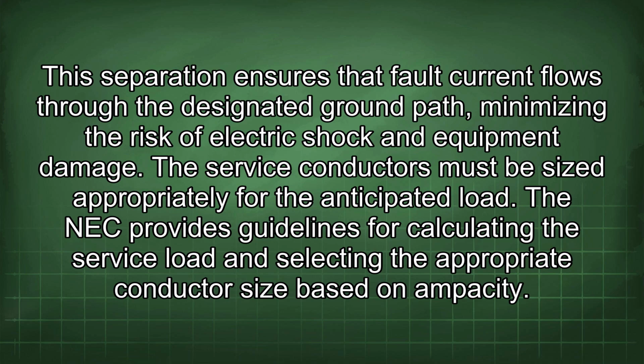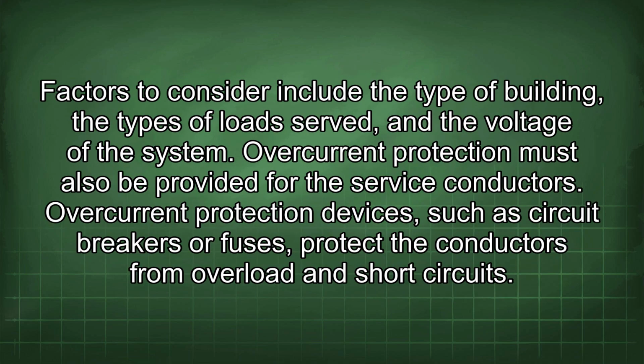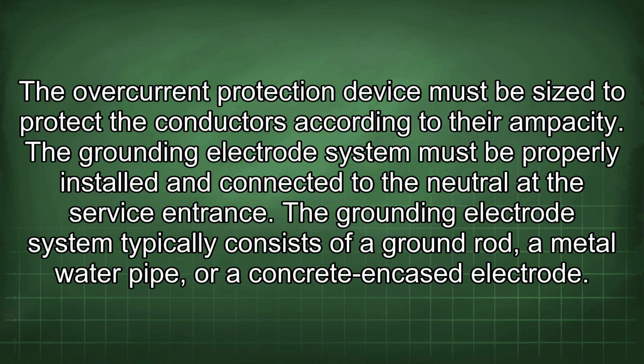The NEC provides guidelines for calculating the service load and selecting the appropriate conductor size based on ampacity. Factors to consider include the type of building, the types of loads served, and the voltage of the system. Overcurrent protection must also be provided for the service conductors. Overcurrent protection devices, such as circuit breakers or fuses, protect the conductors from overload and short circuits. The overcurrent protection device must be sized to protect the conductors according to their ampacity.